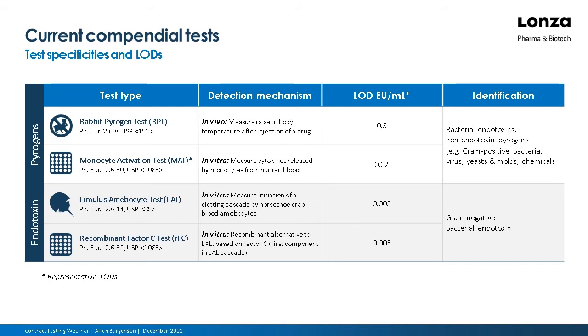But when we get down to the endotoxin-specific assays, we've got limulus amoebocyte lysate, or LAL, and this is compendial all around the world, including EP 2.6.14 as well as USP 85. It's an in vitro measurement measuring initiation of a clotting cascade by the horseshoe crab blood monocytes, or amoebocytes rather. It has a limit of detection even lower than the previous two, of 0.005.